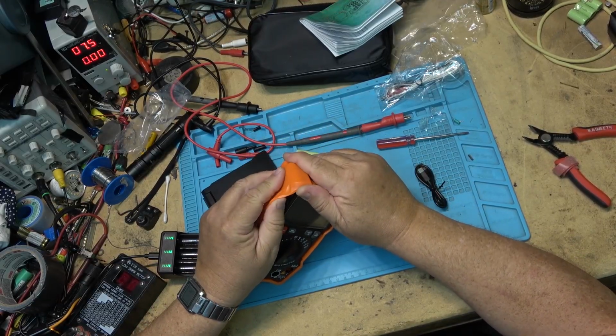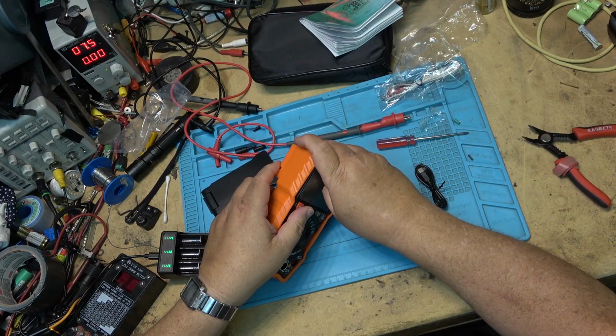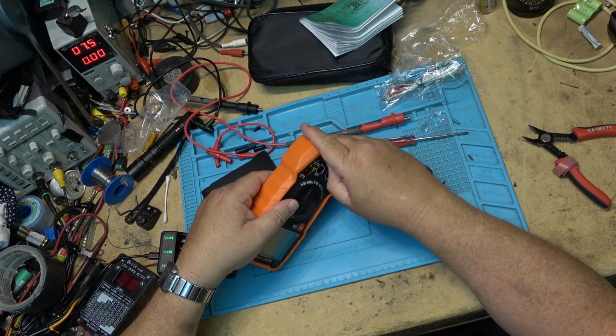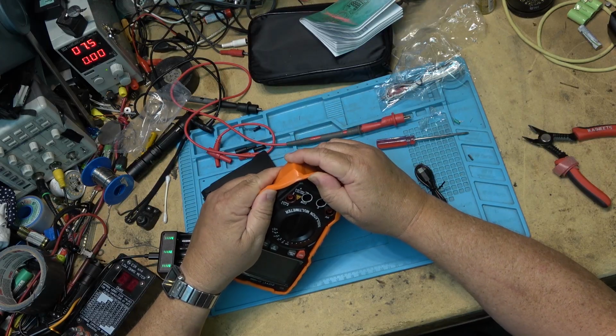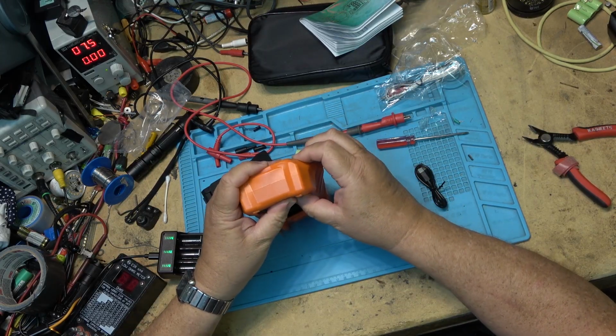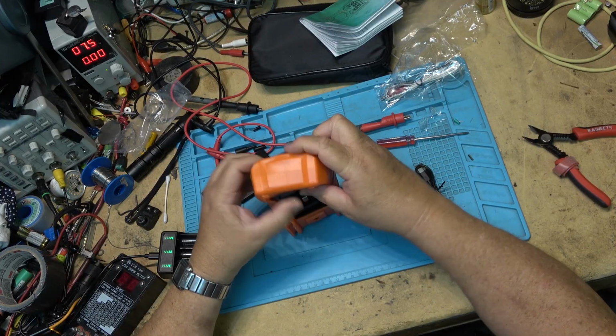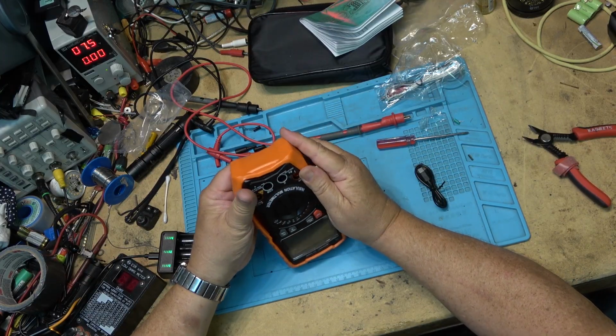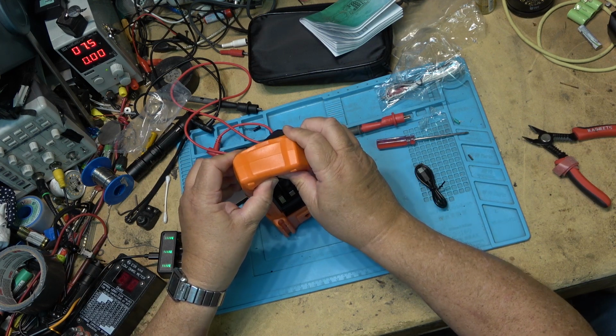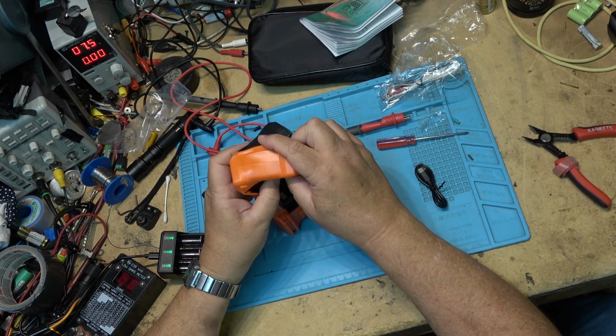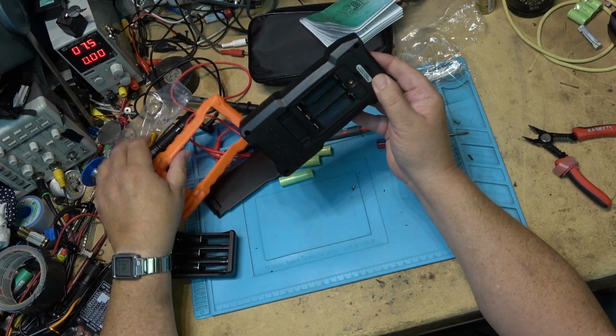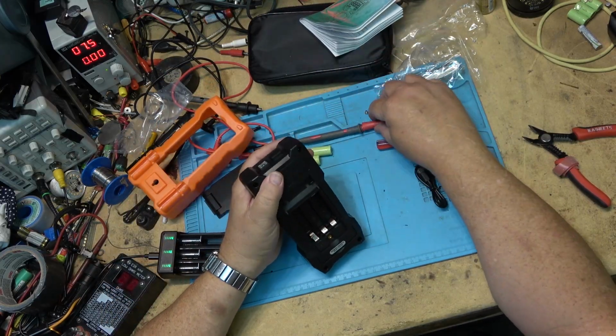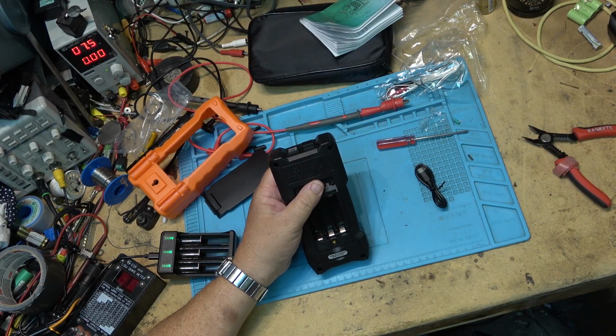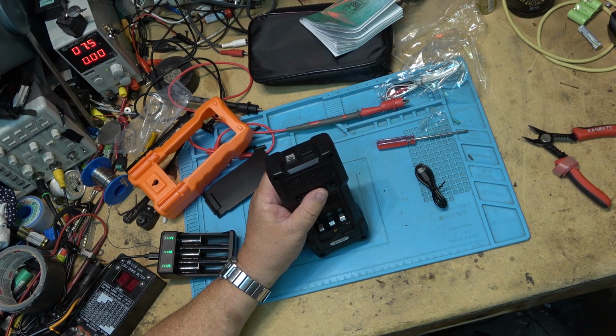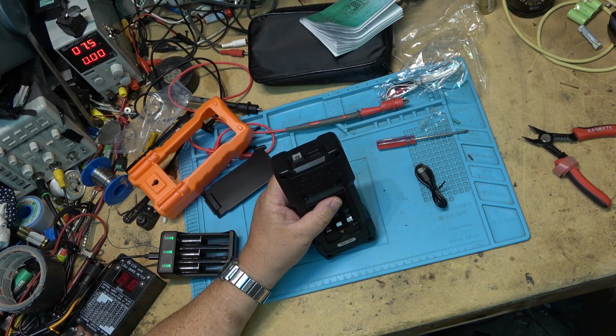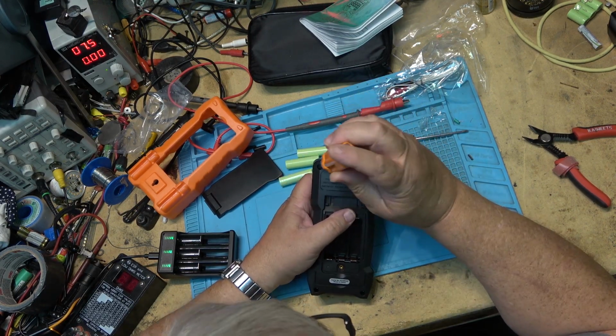I'm going to pop the case off this thing. I want to take a look inside the meter itself, and then maybe we'll do a few more tests on it. I mean, the ohms and volts test, I don't know. I've done the volt test, but the ohms and other tests, do we need to do that? Maybe. This was more of a strength of this meter, is that it can check for breakdown on wire, insulated cable, motors. That's normally where you would test this. Transformers and motors and stuff that could have an internal short is where a meter like this would be most useful. I guess you could test internal wires. If there was a short or breakdown in the insulation, you could check that up to 1,000 volts.